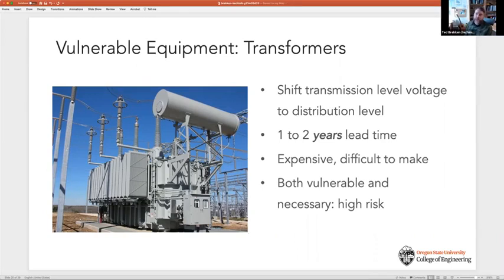Not directly, but if you have loss of generation in one area, that generation is picked up by other generators, so you do open yourself up to the possibility of a cascading failure. That's exactly what was experienced in the large Northeast blackout of 2003, where millions of people across the Northeast were without electricity for many days. That was a classic cascading failure: a fault on one transmission line wasn't a huge problem itself, but it caused power to be redirected in a way that overheated other transmission lines. When transmission lines overheat, the metal literally expands, causing the lines to sag lower. They sagged low enough to fault into trees, causing more transmission line faults, which redirected more power through fewer lines, exacerbating the problem. Pretty soon it spirals out of control, and massive parts of the grid switch off—that's a very large failure. So you can have that kind of cascading failure, but otherwise there's not really any other direct connection between them, if I'm interpreting your question correctly.